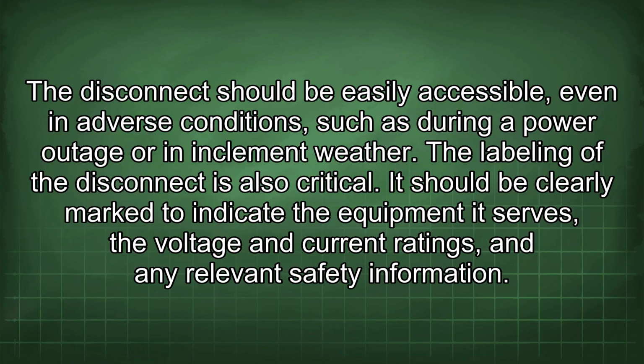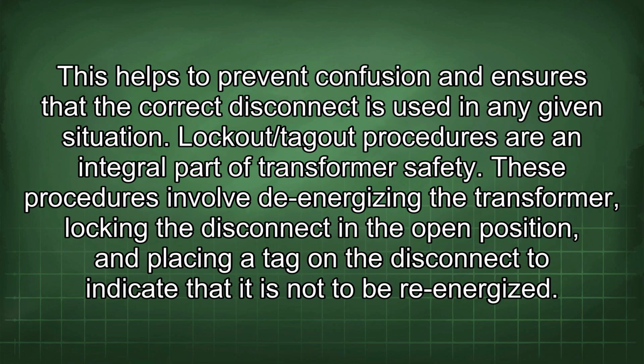The labeling of the disconnect is also critical. It should be clearly marked to indicate the equipment it serves, the voltage and current ratings, and any relevant safety information. This helps to prevent confusion and ensures that the correct disconnect is used in any given situation. Lockout/tagout procedures are an integral part of transformer safety. These procedures involve de-energizing the transformer, locking the disconnect in the open position, and placing a tag on the disconnect to indicate that it is not to be re-energized.